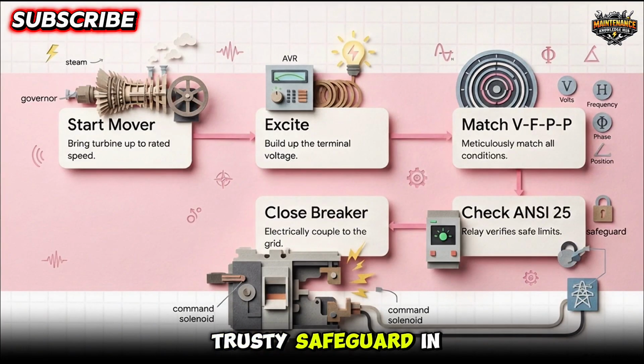So, with our trusty safeguard in place, we can look at this whole sequence as a pretty straightforward block diagram. Step 1, you start the prime mover, using the governor to bring the turbine up to its rated speed. Step 2, you establish excitation, using the AVR to build up the generator's voltage. Step 3, you meticulously match those VFPP conditions. Step 4, the ANSI 25 relay double-checks all the work and gives the green light. And finally, Step 5, the close command is issued. The breaker snaps shut, and boom, the generator is successfully electrically coupled to the grid.